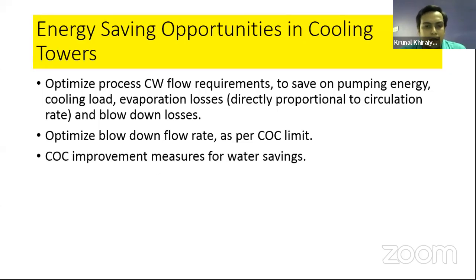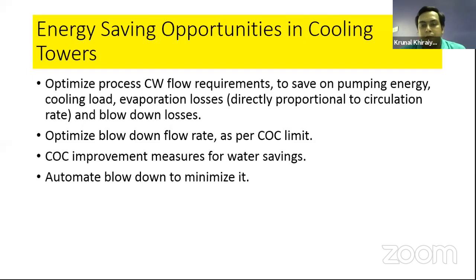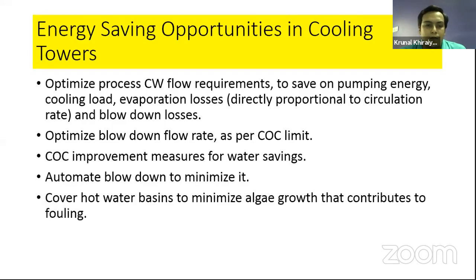COC improvement, yes. Water conservation. Sometimes people are not operating the blowdown pipes or blowdown valves, because in most industries the blowdown valve is a manually operated valve. The technicians responsible for operating this valve sometimes do not operate it on a regular basis, so COCs may increase, which can choke your nozzles. Instead, to avoid this kind of operational trouble, you need to use automatic blowdown systems, so that at regular intervals some of the water is blown down and it cannot create other problems in the system.